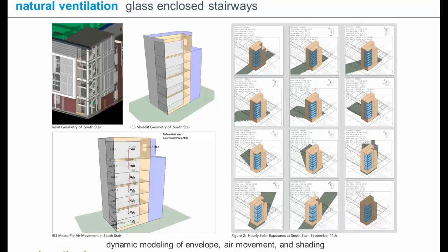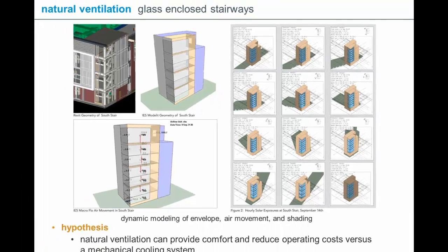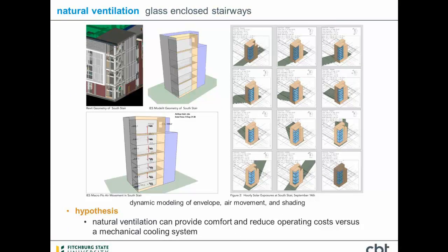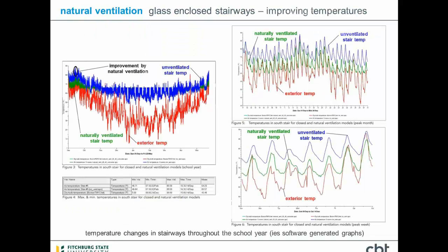We also looked at a number of different control programs: when the louvers should open before the temperature got to a certain point, when they should close, and different types of louver sizes, and we ran a number of simulations to show that. In terms of the output, what you see in red here is the exterior temperatures throughout the year, and you get the cooling loads and the building energy loads throughout the year.